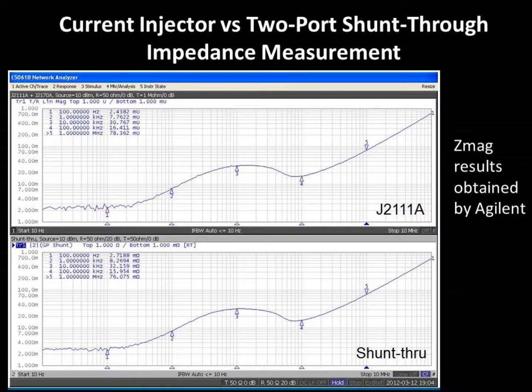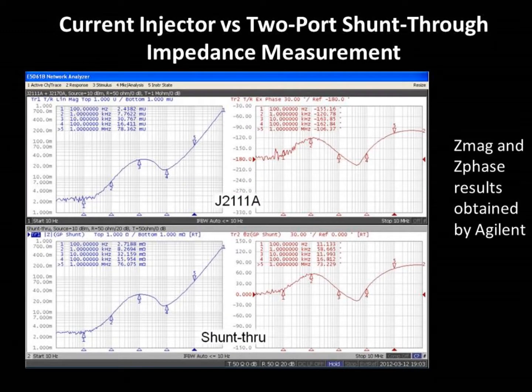These are the results they obtained when measuring the magnitude of the impedance. Here the results are expanded to show the phase of the impedance measurements. As you can see, the current injector and two-port shunt-through measurements are in close agreement, and the results for magnitude and phase are quite good, even in values as low as 2 milliohms.